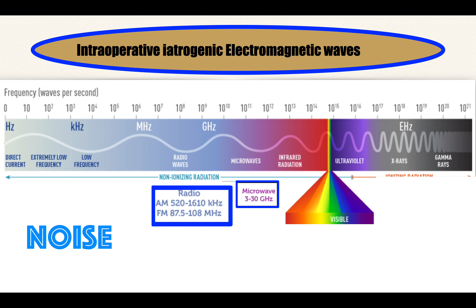Diathermy electrosurgical unit: radio frequency induces alternate vibrations of tissue ions that result in maximum heat, which effects cutting and coagulation, hence bloodless surgery.